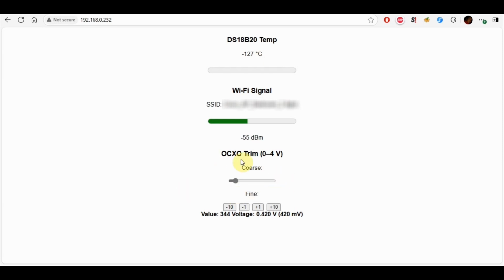So going on first startup, obviously we're going to get a really big swing from high to low, and then it'll start averaging out. But what we do is we can slide this slider up and down, or we can just simply add just a few millivolts here, and that will go up fine and coarse, and we can obviously keep an eye. At the moment it's on 10 megahertz, so 10.0001002. So we're going to add a little bit of voltage. Obviously you can't see that. I'm going to add just a fraction more to compensate. Now we're back onto 10.